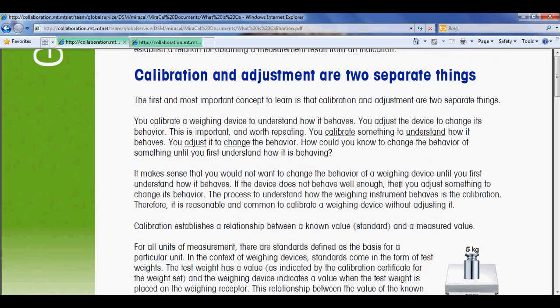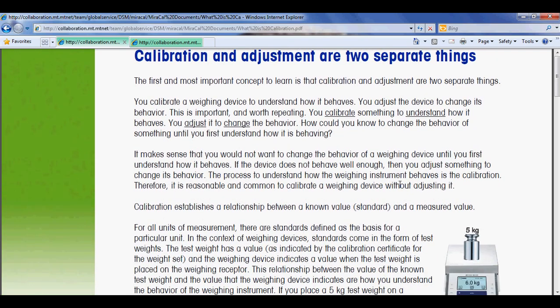So the first and most important thing to note is that calibration and adjustment are 2 separate things. You calibrate a weighing device to understand how it behaves, and you adjust that device to change its behavior. And again, that's very important and worth repeating. So you calibrate something to understand how it behaves, and then you adjust it to change the behavior. So how could you know how to change the behavior of something, or how would you know that you even need to change the behavior of something until you first understand how it is behaving? You could not do that.